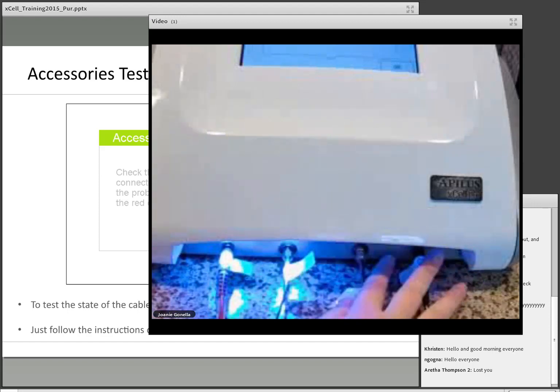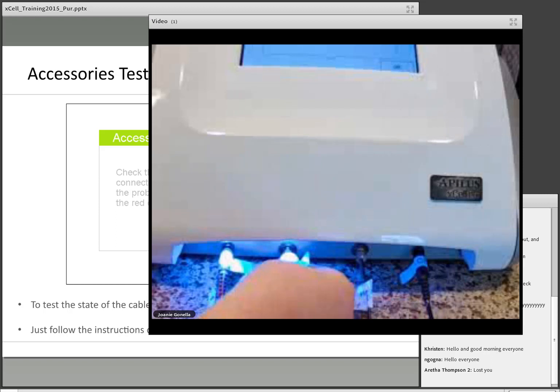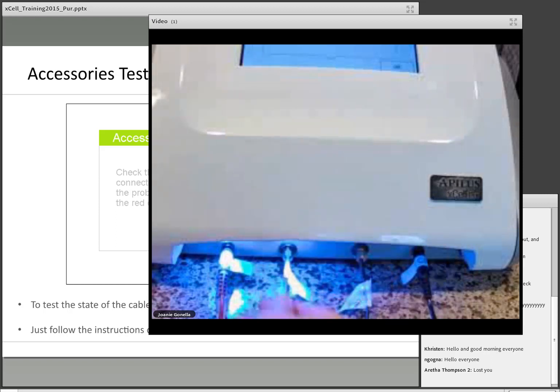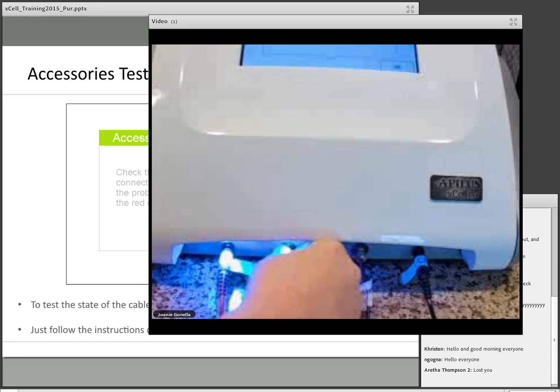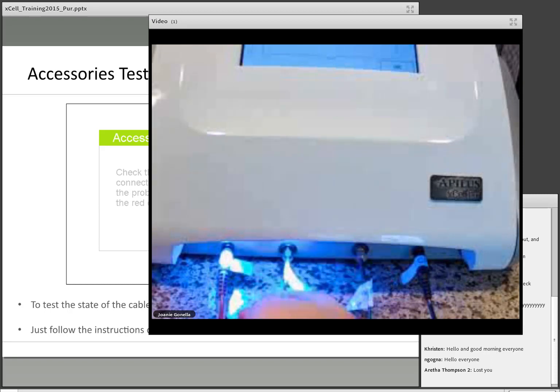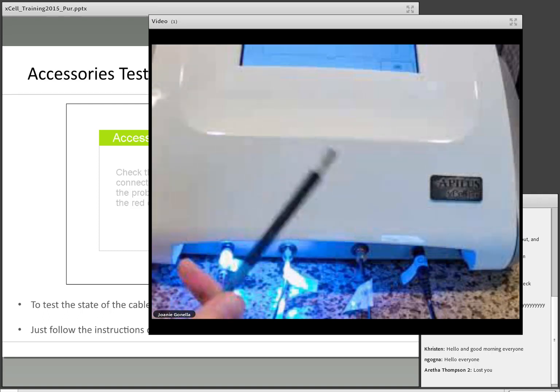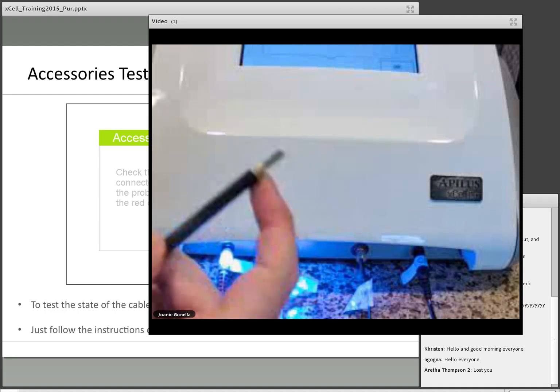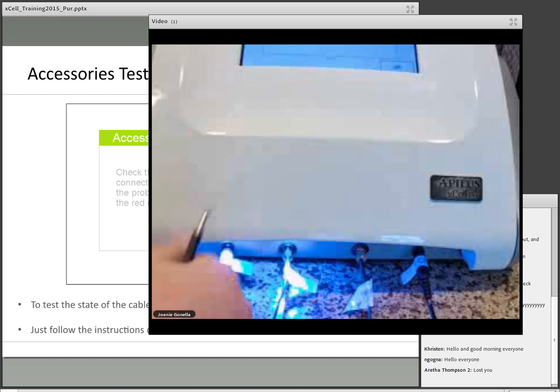I'm not testing these right now. This is probe holder A, this is probe holder B. So check that probe holder A, the one to the left, is well connected. Okay, so I'm going to tighten this, looks good. Remove the plastic cap from the probe holder. I don't have a cap on here, so you want to expose the prongs. And then you're going to insert the prongs into the red connector.